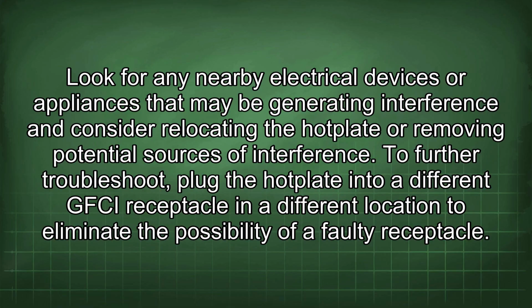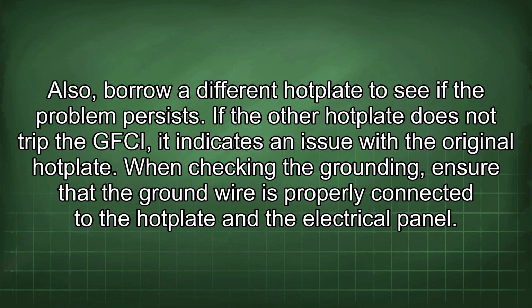To further troubleshoot, plug the hot plate into a different GFCI receptacle in a different location to eliminate the possibility of a faulty receptacle. Also, borrow a different hot plate to see if the problem persists. If the other hot plate does not trip the GFCI, it indicates an issue with the original hot plate.